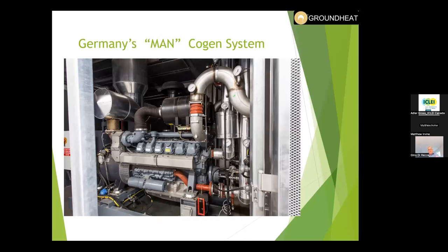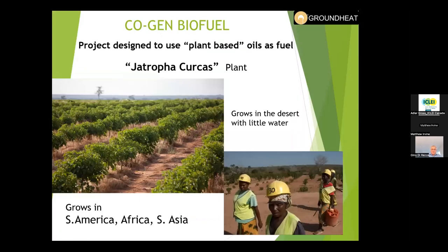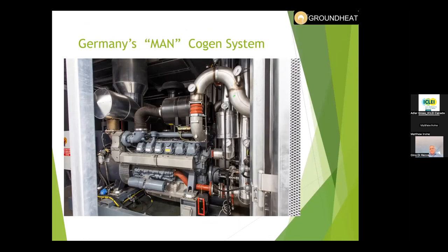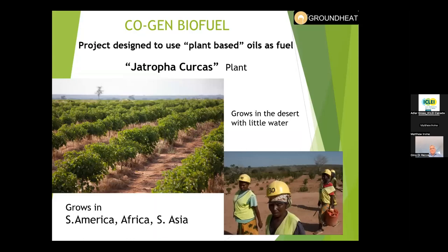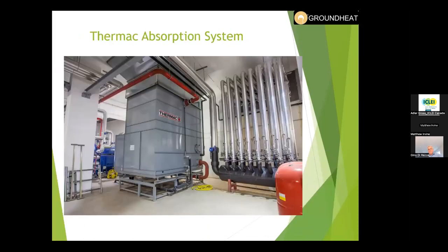This is a German cogen that they use as a backup for heat, and also use the discharge heat for cooling. I'll show you that later. This cogen uses diesel, but the diesel is made from a plant-based oil as fuel. It's called the Jatropha curcas plant. It grows in South America, Africa, and South Asia in deserts. It needs very little water. So the cogen hot water goes into the absorption system and creates chilled water.